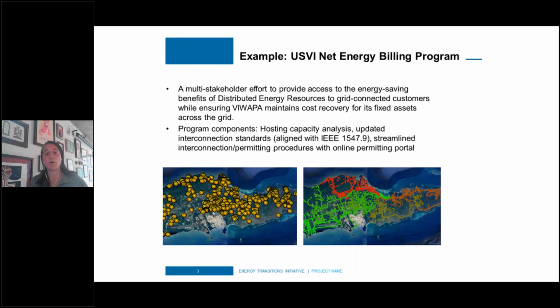There was a technical component to it, which consisted of doing a complete update to the utility's interconnection standards to align with the latest from IEEE. So they are now in compliance with IEEE 1547.9.